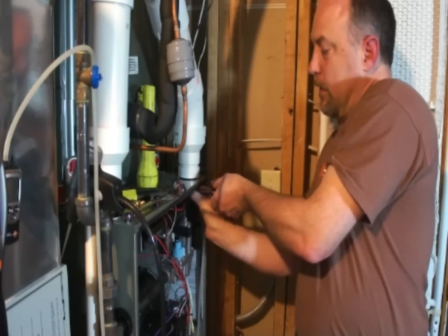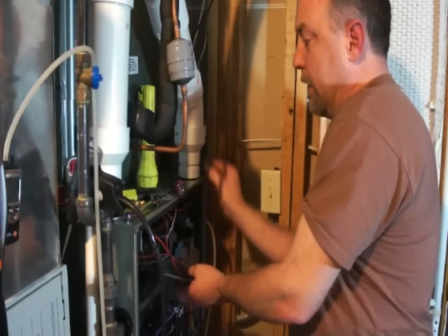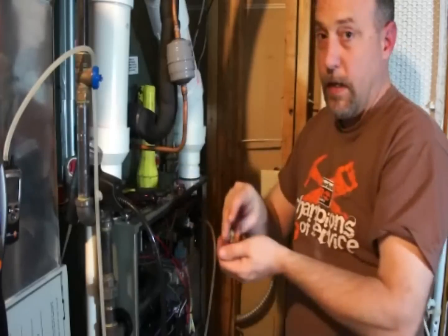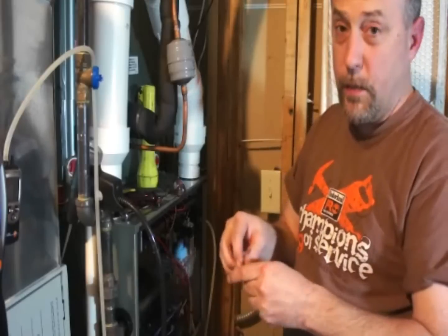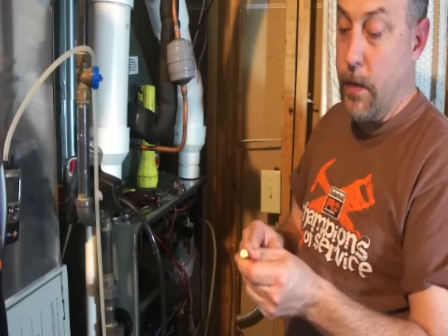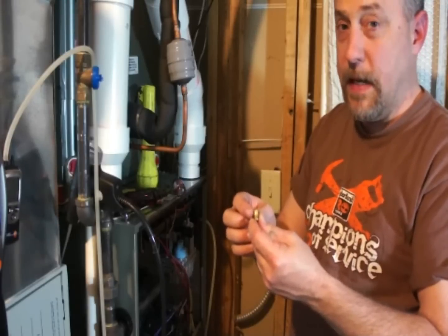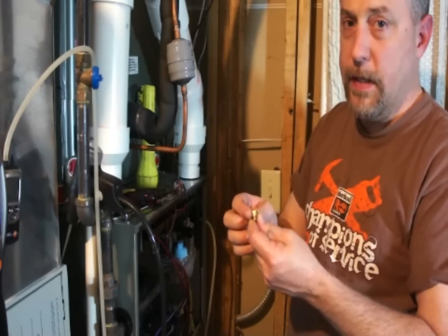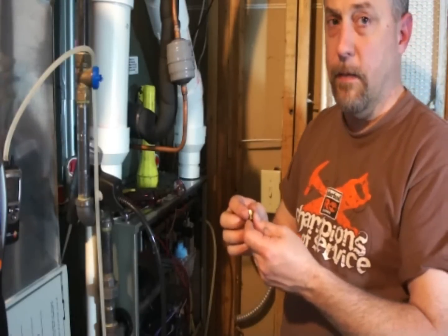I've got the manifold out here. I've got six brand new orifices — these are number 49s; the ones that were in there are number 50s. I ordered them right from Rheem and we're going to go ahead and swap these out, check the fuel pressure again, run a combustion analysis, and check the input.